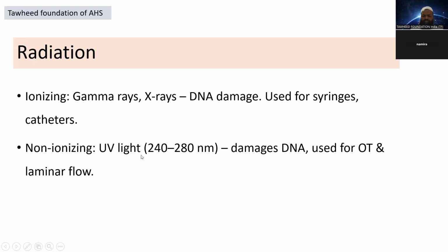Infrared radiation and UV radiation come under non-ionizing radiation. Gamma rays and X-rays are used for mass sterilization of syringes and catheters. UV radiation with a wavelength of 240 to 280 nanometers has bactericidal capacity. The UV radiation causes protein denaturation and interferes with DNA replication of bacteria. UV radiation is used for sterilization of closed areas, surfaces, operation theaters, OT, laminar airflow, etc.